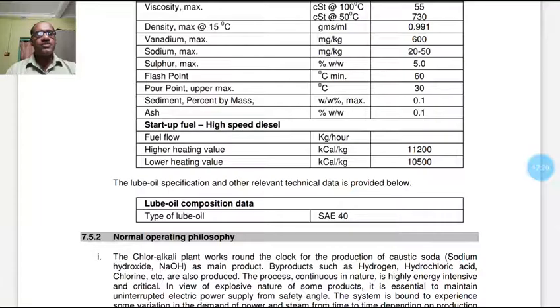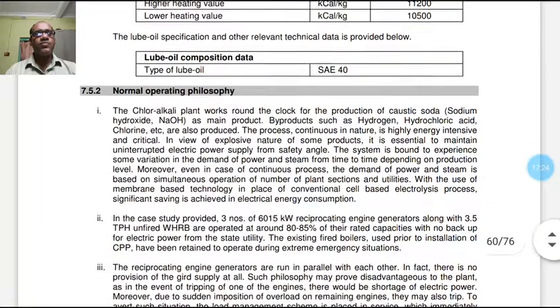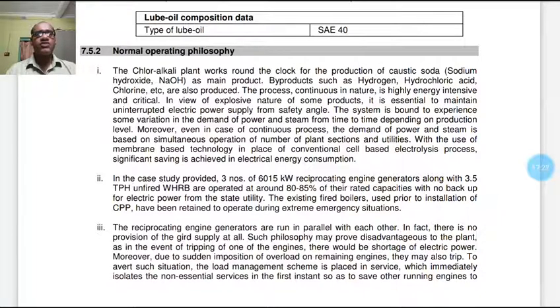Normal operating philosophy. The plant works around the clock for the production of caustic soda, that is sodium hydroxide NaOH, as main product. Byproducts such as hydrogen, hydrochloric acid, chlorine, etc. are also produced. The process, continuous in nature, is highly energy intensive and critical. In view of the explosive nature of some products, it is essential to maintain uninterrupted electric power supply from safety angles. The system is bound to experience some variation in demand of power and steam from time to time depending on production level.